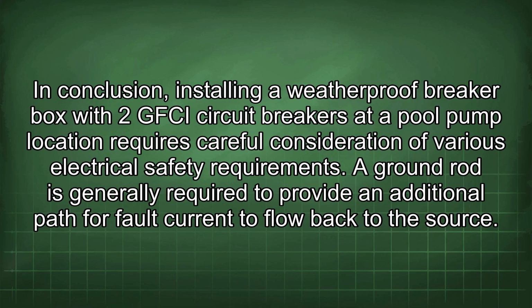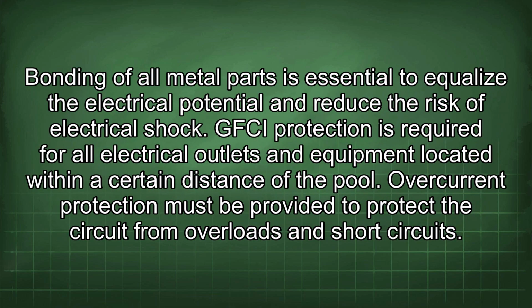In conclusion, installing a weatherproof breaker box with 2 GFCI circuit breakers at a pool pump location requires careful consideration of various electrical safety requirements. A ground rod is generally required to provide an additional path for fault current to flow back to the source. Bonding of all metal parts is essential to equalize the electrical potential and reduce the risk of electrical shock. GFCI protection is required for all electrical outlets and equipment located within a certain distance of the pool. Overcurrent protection must be provided to protect the circuit from overloads and short circuits.